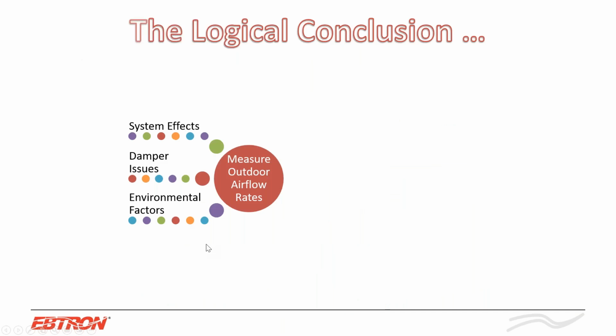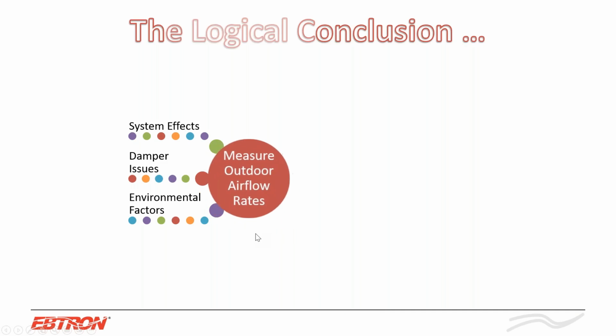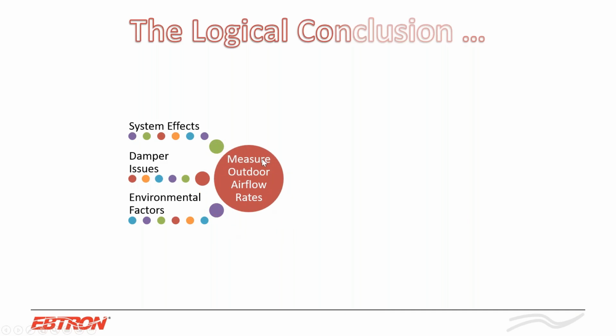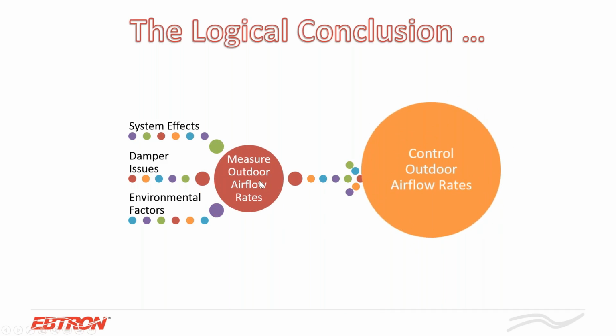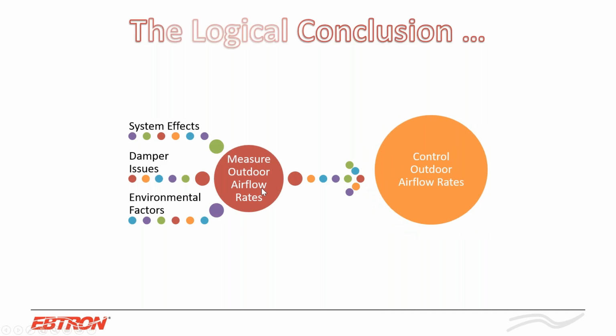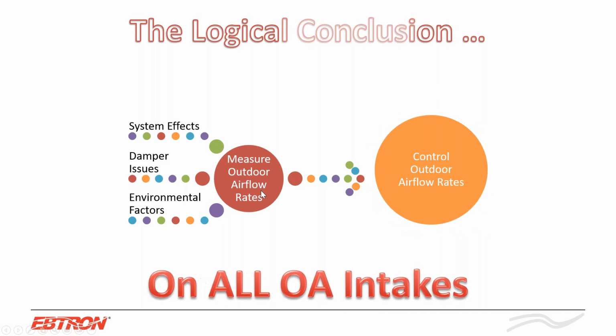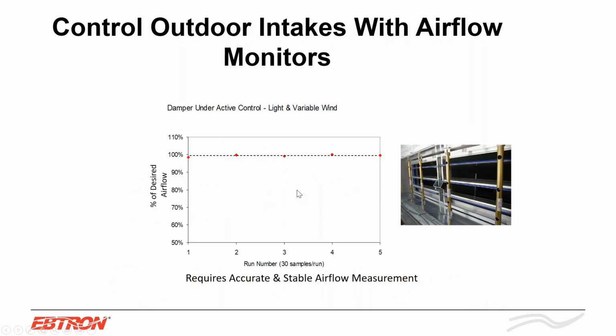So you really got to measure outdoor airflow rates because you have all of these issues, and you have to control them to make sure you're bringing in the right amount of outside air to the space. Now, this just looks at the simulation I was talking about earlier. When we measured it with a flow meter and we controlled that damper, we were right at 100% of the desired airflow set point.